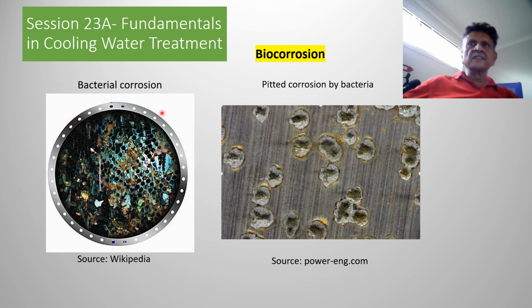The pictures in this slide show how the corrosion will look. If you notice all the parts that are corroded, this is the header of the chiller plate, and the little big holes are the holes of the pipes through which water flows for cooling, and the copper is corroded to copper sulfate, the blue color. So you find that a lot of corrosion takes place.